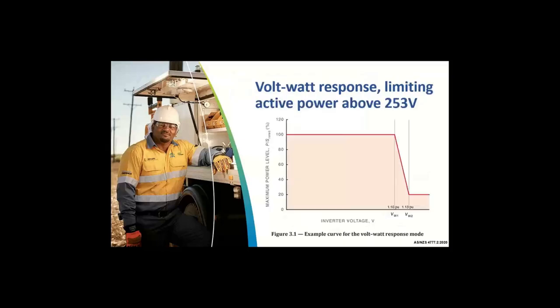In addition, where voltages are observed locally to rise above the limit of 253 volts, the volt-watt response requires inverters to limit their maximum active power output to prevent further over voltage being caused. And so that ramps down the active power limit from 100% down to 20% at about 260 volts.